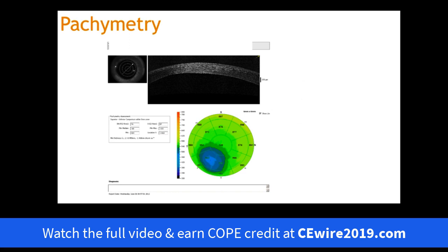With OCT technologies, we really take this concern out of the equation. In particular, for the central cornea, we always have a perpendicular reading of the central corneal thickness. If you're currently using an ultrasound probe and transition to OCT pachymetry, you'll often find that the corneal thickness reads somewhat less. This matters because if we're measuring at an artificially thicker value, we may be placing ocular hypertensive patients in a safer risk zone than they actually belong, and OCT gives us a true read.